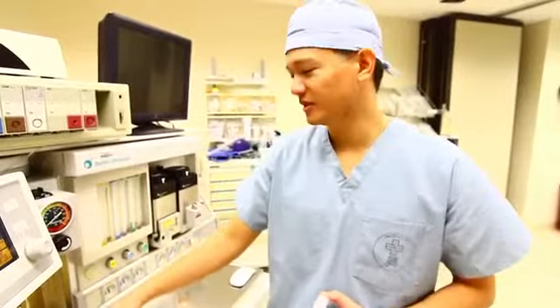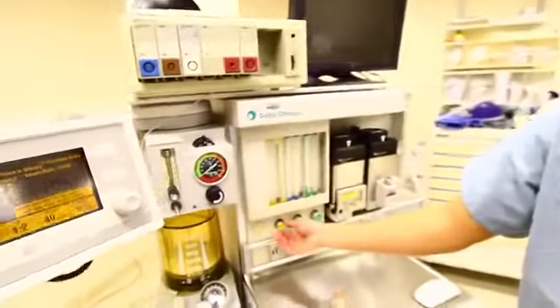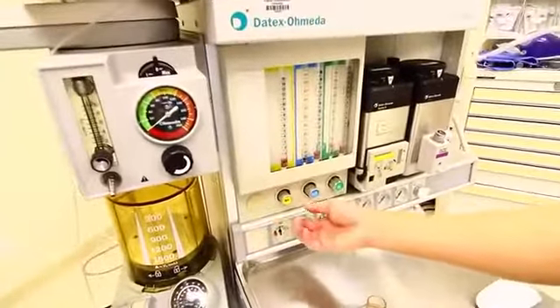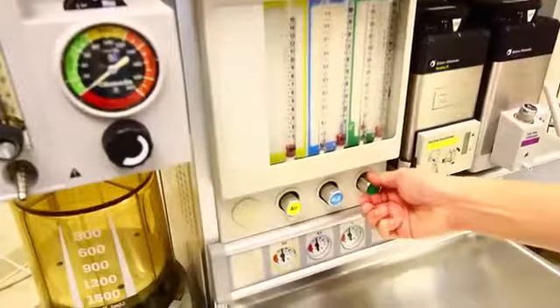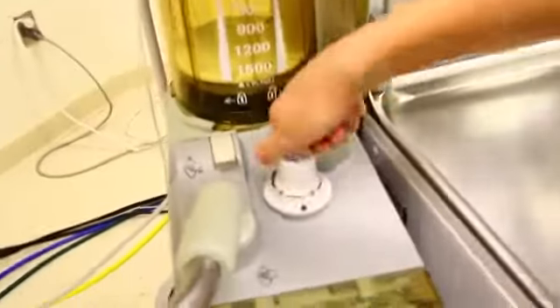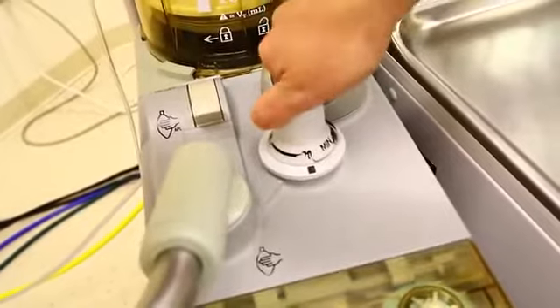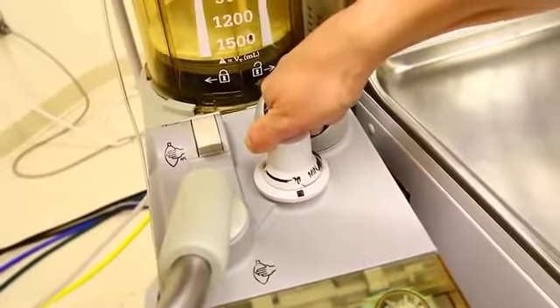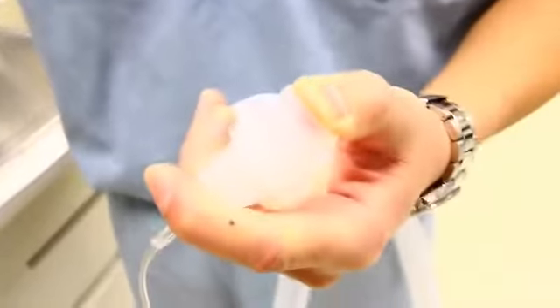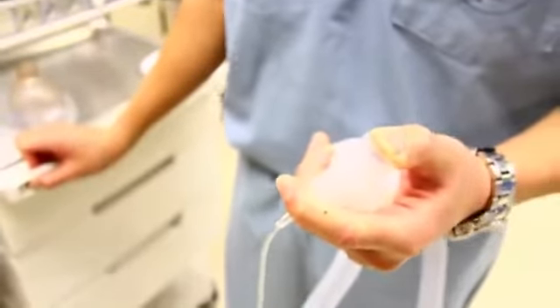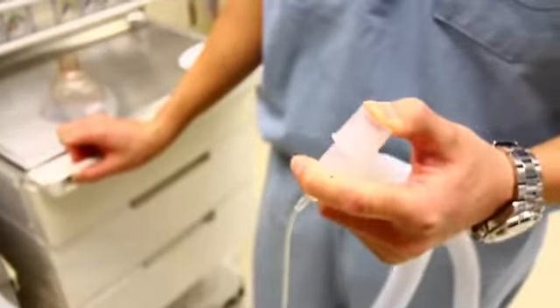The next thing is to perform a leak check of the breathing system. You want to ensure that all the flows are set to 0 or minimum. You want to close the APL pop-off valve by turning it clockwise. You want to occlude the Y piece and then use the oxygen flush valve to pressurize the system to 30 centimeters of water.